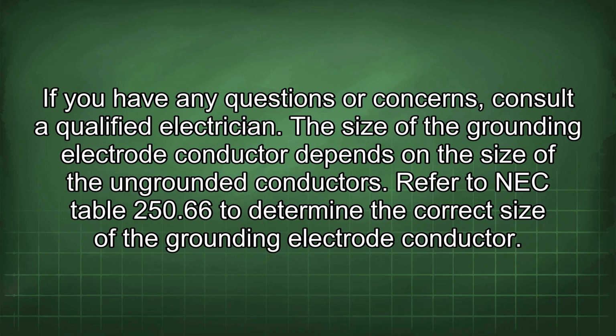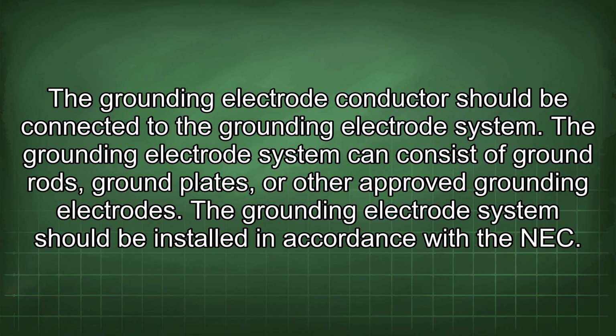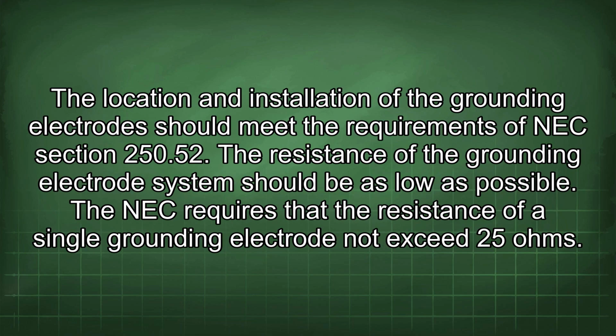The size of the grounding electrode conductor depends on the size of the ungrounded conductors. Refer to NEC Table 250.66 to determine the correct size of the grounding electrode conductor. The grounding electrode conductor should be connected to the grounding electrode system. The grounding electrode system can consist of ground rods, ground plates, or other approved grounding electrodes. The grounding electrode system should be installed in accordance with the NEC. The location and installation of the grounding electrode should meet the requirements of NEC Section 250.52.